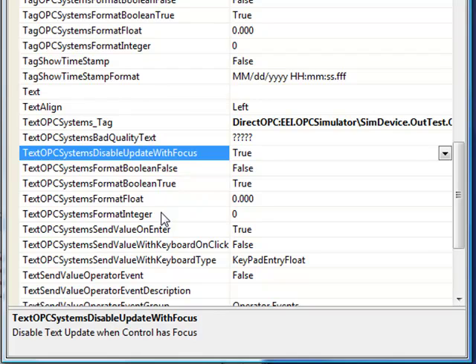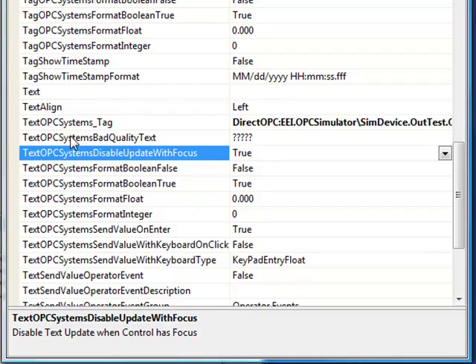We also have the property called text OPC systems disable update with focus. With this set to true, when the focus is in the text box, dynamic data will not update the text box. This makes it operator friendly that when they're entering a new value that their entry will not be overwritten from a value. When they leave focus from the text box, it will return back to the current value of the OPC systems dot net tag. Let's see what this looks like in action.